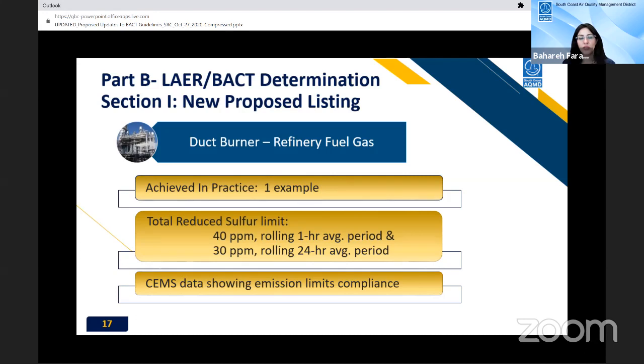We have one achieved-in-practice example with more than 6 months of supporting CEMS data. We looked at 6 months of continuous emission monitoring data from this unit, and those numbers confirm that the permit limit, established at 40 ppm rolling 1-hour average and 30 ppm rolling 24-hour average, is actually effective.